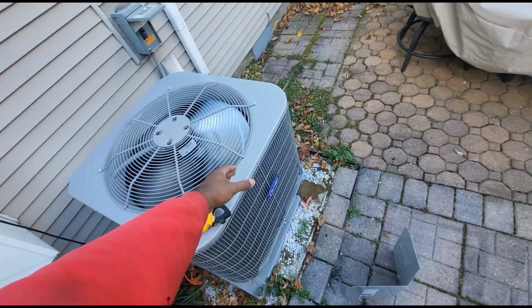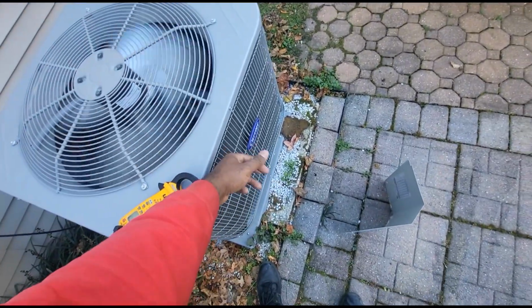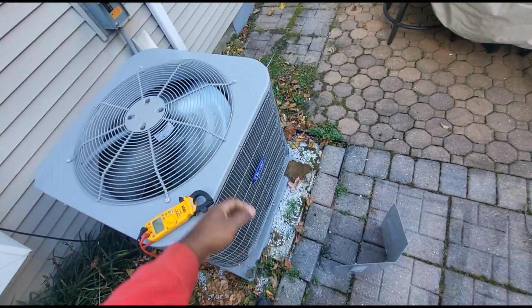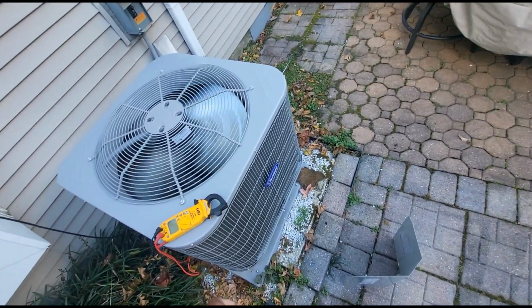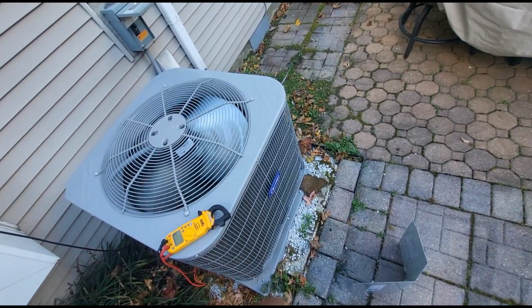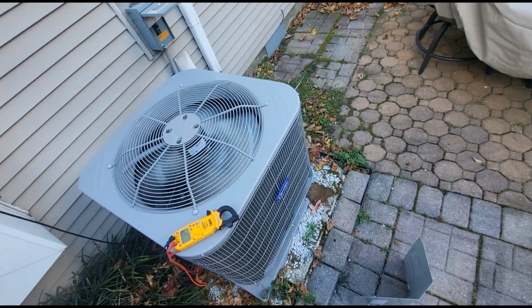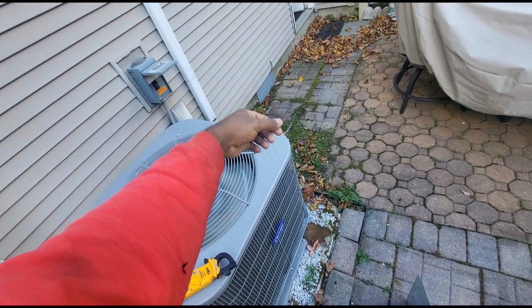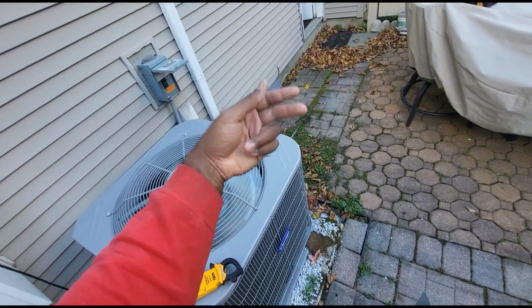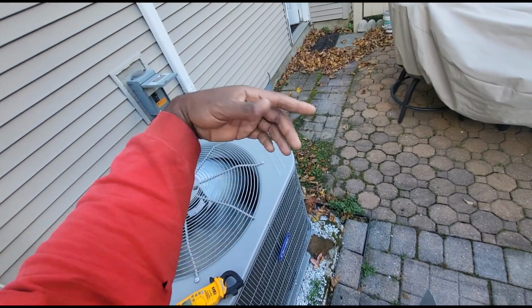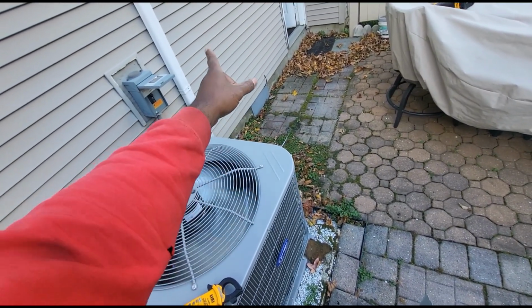Heat pumps are great, but below a certain point, to prevent the coil from freezing and to prevent this heat pump from damaging itself, this heat pump needs to turn off on defrost. And if this heat pump turns off on defrost, whatever your backup heat is, whether it be electric, propane, gas, or oil, your backup heat will need to run to maintain the set point in the house.